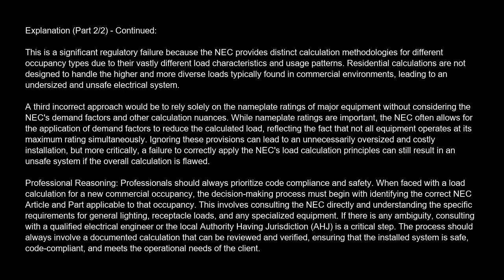This involves consulting the NEC directly and understanding the specific requirements for general lighting, receptacle loads, and any specialized equipment. If there is any ambiguity, consulting with a qualified electrical engineer or the local authority having jurisdiction, AHJ, is a critical step. The process should always involve a documented calculation that can be reviewed and verified, ensuring that the installed system is safe, code compliant, and meets the operational needs of the client.